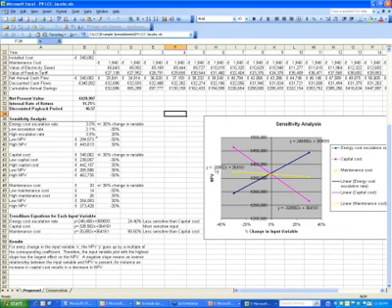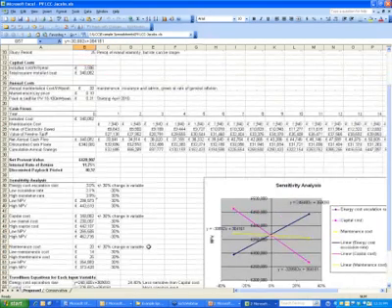This is some sensitivity analysis. This is what's called a spider chart. And a few different variables. I looked at energy cost escalation rate, did plus or minus 30% on that value and see what it did to net present value. And that ended up with this navy blue line, and did capital costs and maintenance costs as well. And basically you can tell by the slope of this line which one affects the overall result the most. And so I did the regression equations here. Highest slope was capital costs, that had the largest effect.